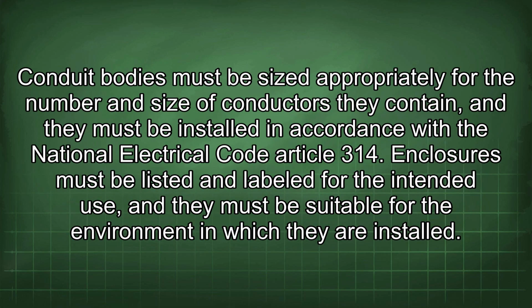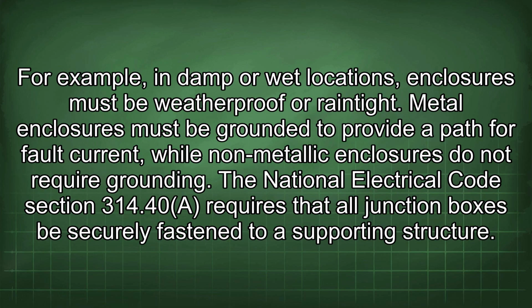Conduit bodies must be sized appropriately for the number and size of conductors they contain, and they must be installed in accordance with the National Electrical Code Article 314. Enclosures must be listed and labeled for the intended use, and they must be suitable for the environment in which they are installed. For example, in damp or wet locations, enclosures must be weatherproof or rain-tight.